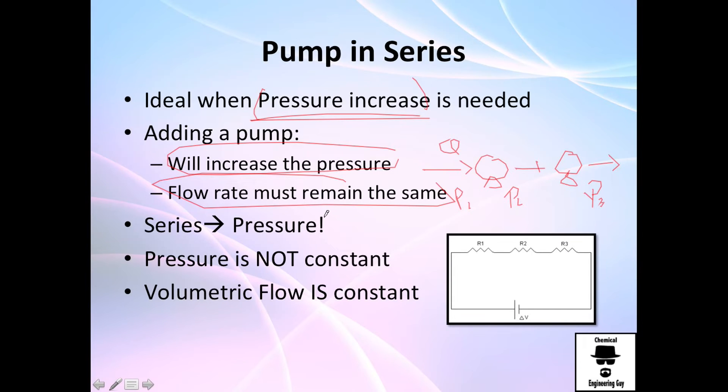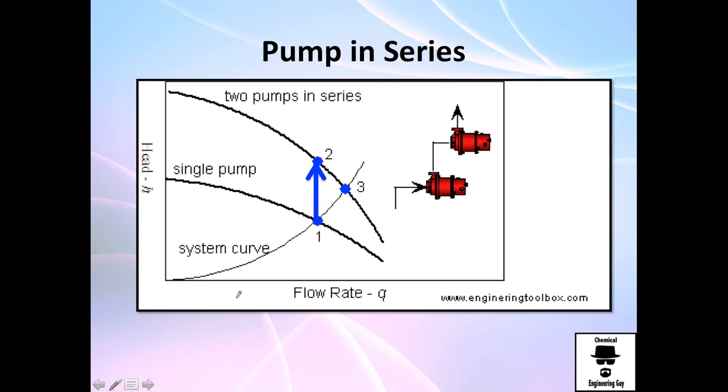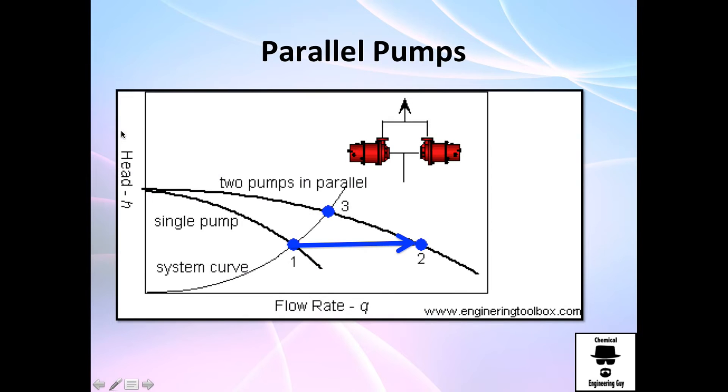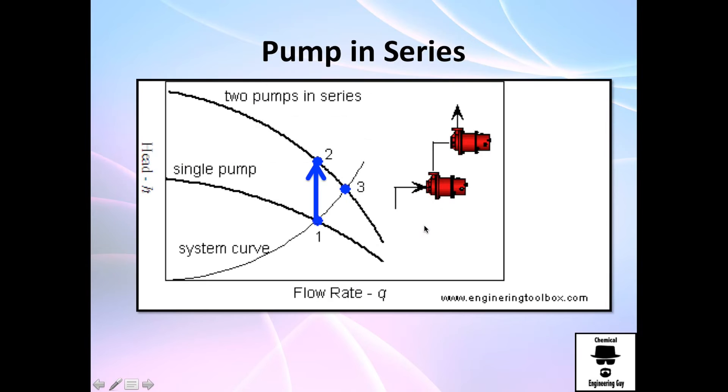So, when you arrange in series, you are looking out for a pressure increase. And then, what's going to happen is, you have your system curve here, and this is the single pump. This will be the normal operation, but when you add another in series, so you have these pumps, what you are going to do is increase the head. Previously, we were increasing the flow rate, now we are increasing the head of the system.